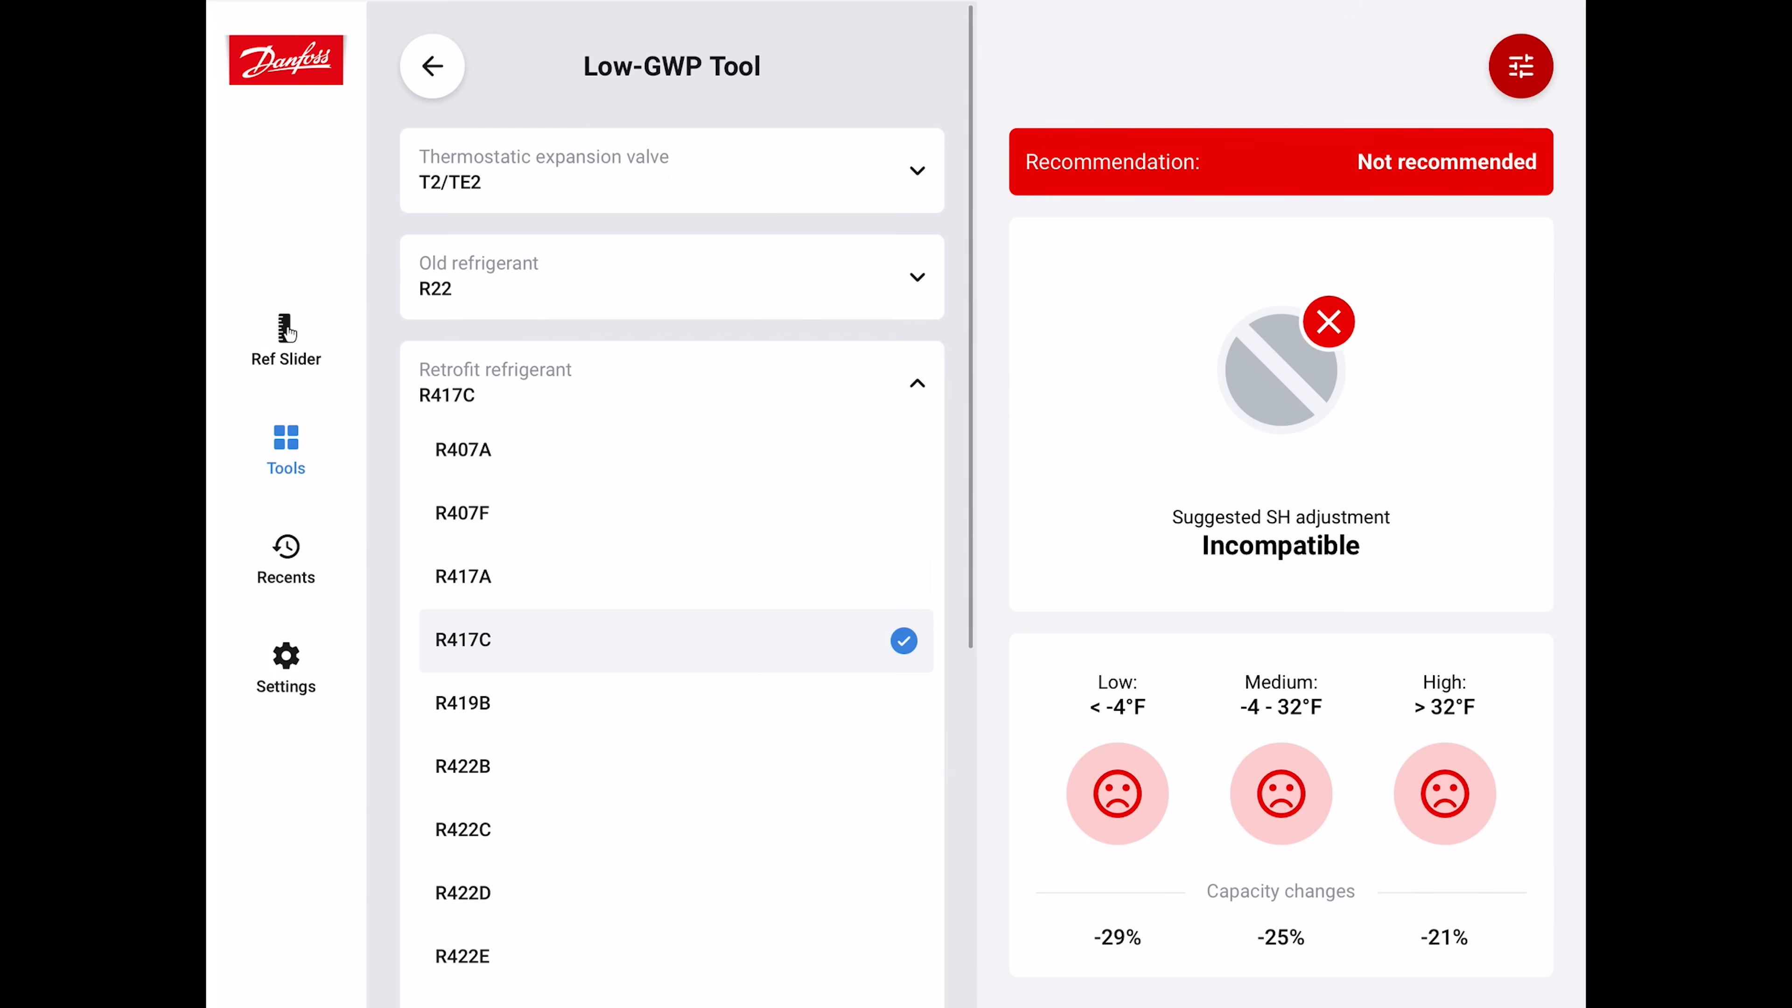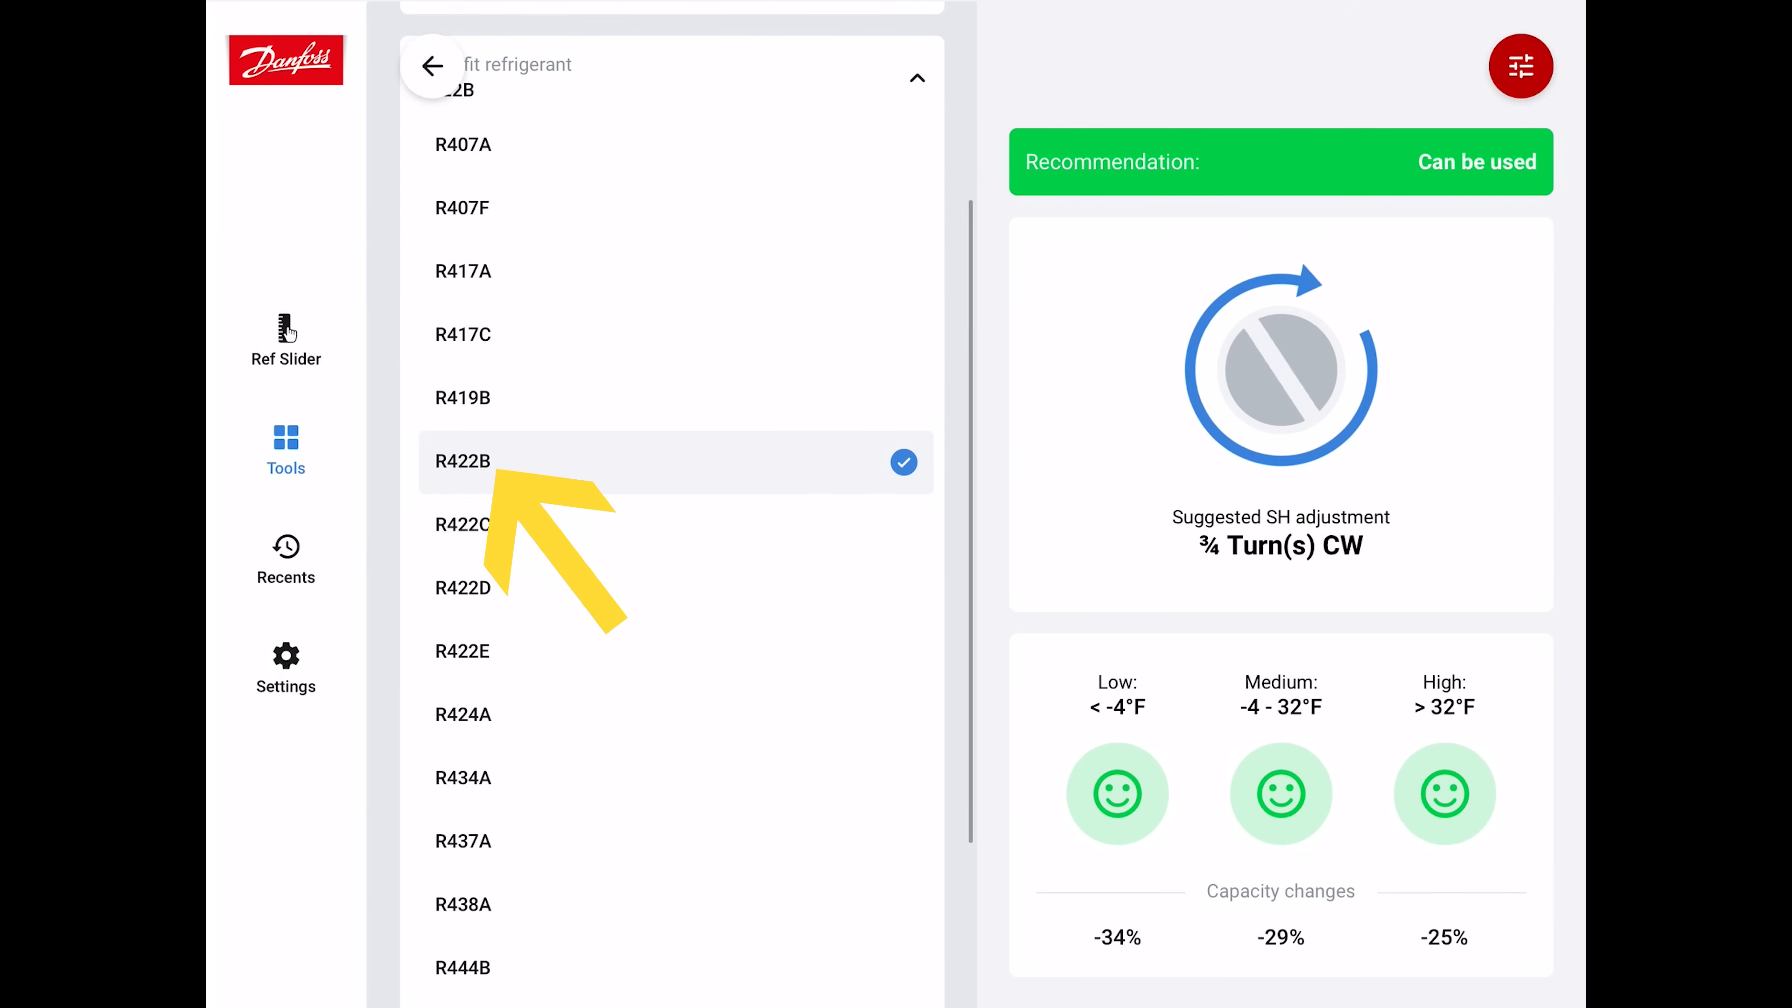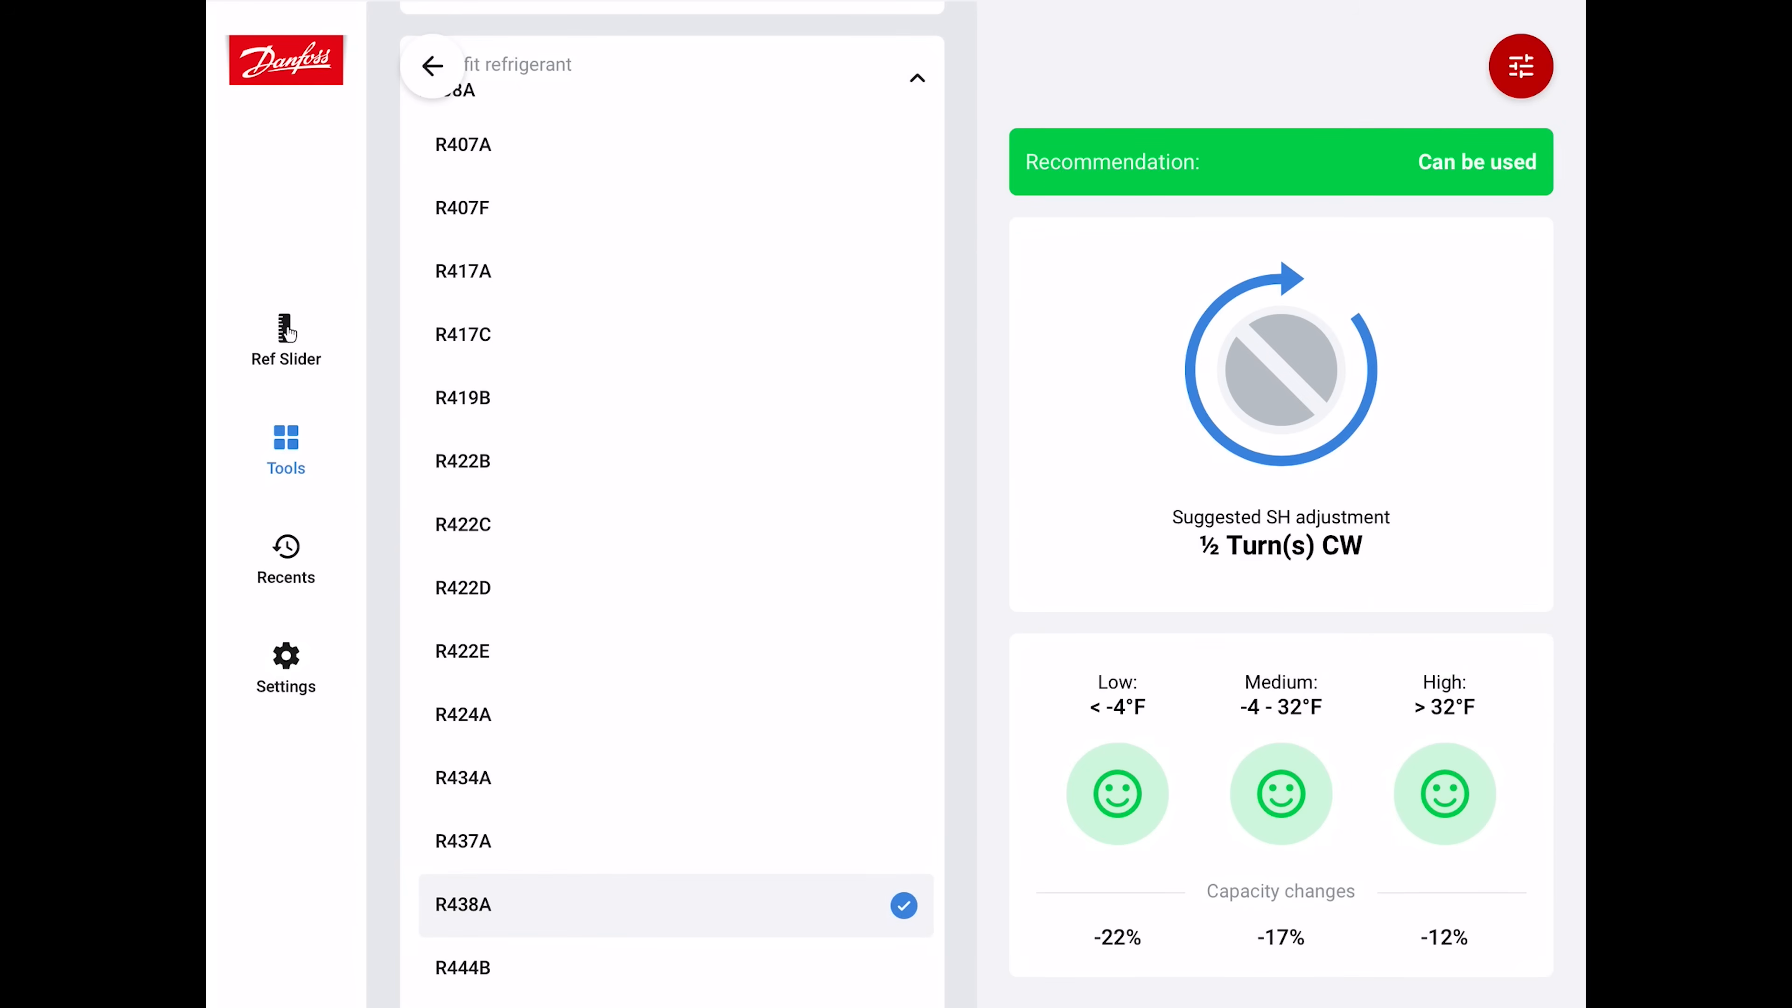Let's find another refrigerant such as R422B. It's saying you're going to lose some capacity if you were to put R422B in. For a high pressure system, it looks like you're going to lose quite a bit of capacity. To increase the efficiency of the system, you should adjust the superheat three quarters of a turn clockwise. Compared with the R438A, that's only half a turn clockwise and the capacity loss for a high pressure system is less.